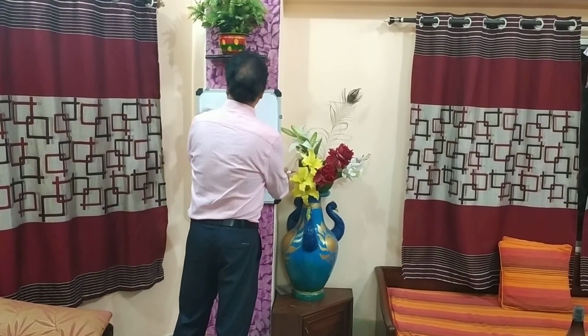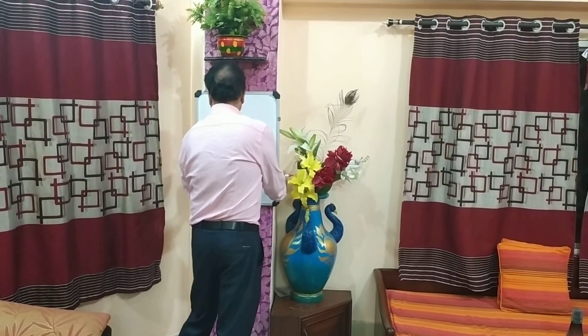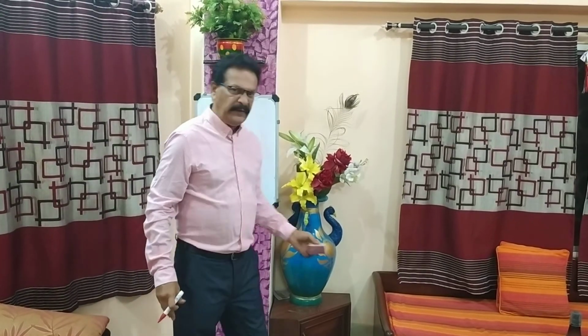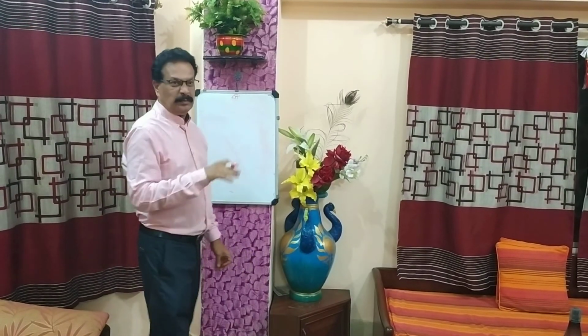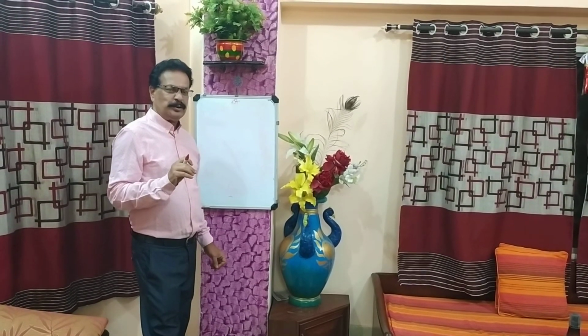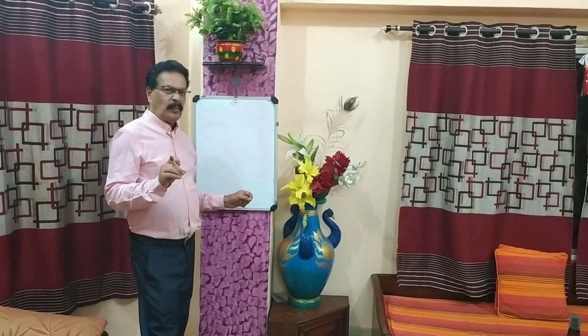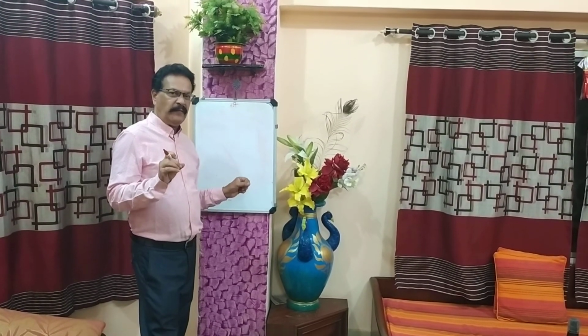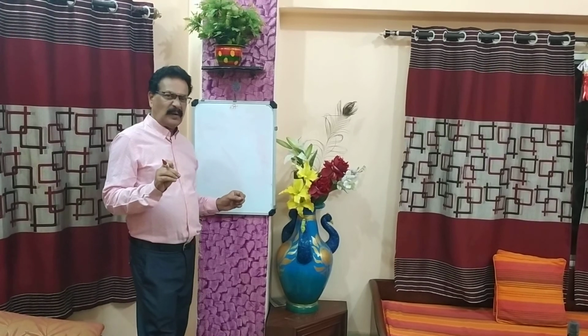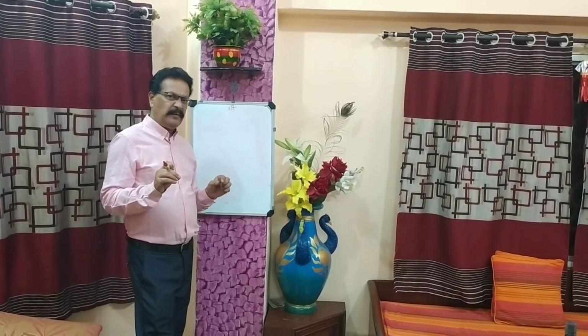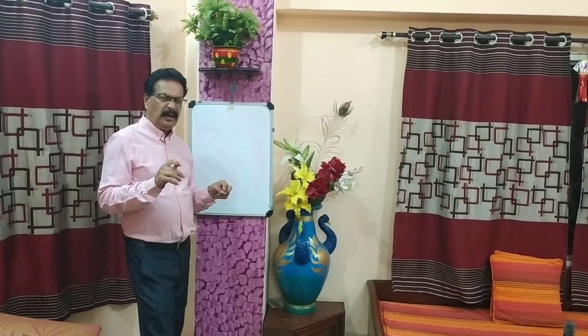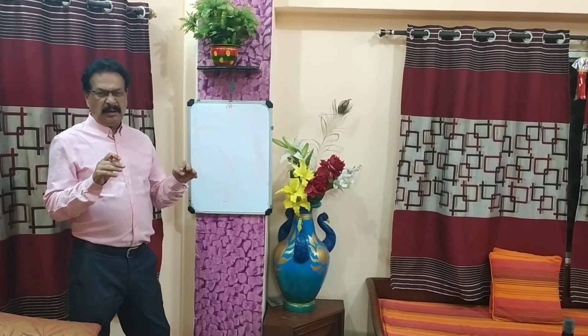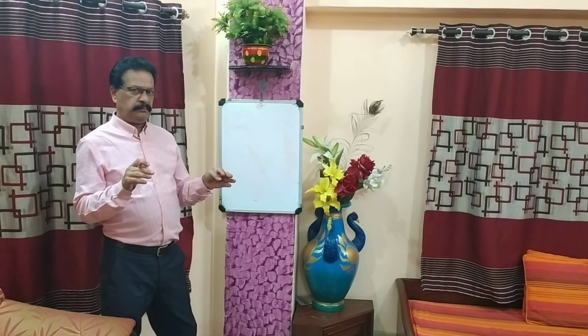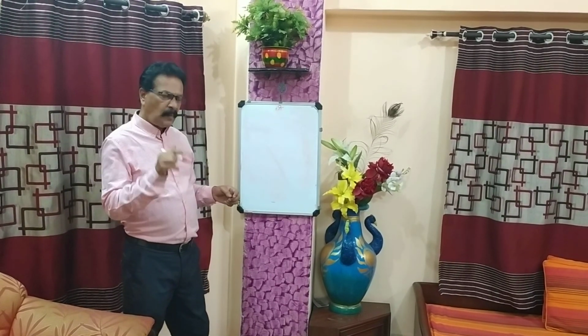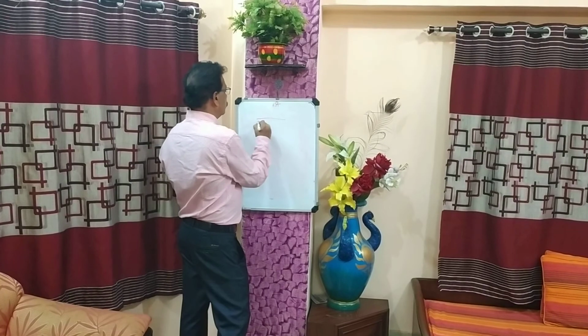As per the perfect rules and perfect specifications, 22 things - the plate should be at least minimum 4 feet by 4 feet, totally galvanized. The strip should be galvanized, the nut board should be galvanized, it should be dipped in coal, charcoal, salt, then black cotton soil. Then 2 funnels should be there in the system.